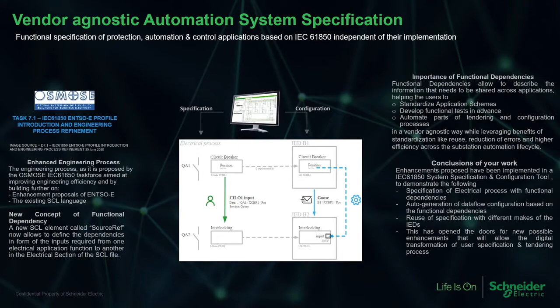This evolution of the engineering process makes it possible to automate a significant part of a system configuration based on data exchanges defined at the specification phase, to produce a complete data flow at IED level without human interaction. It is an enabler for utilities for introducing IEC 61850 during the creation of their own specification, with reduced effort and with assurance that the resulting configuration will be closer to the original requirements.